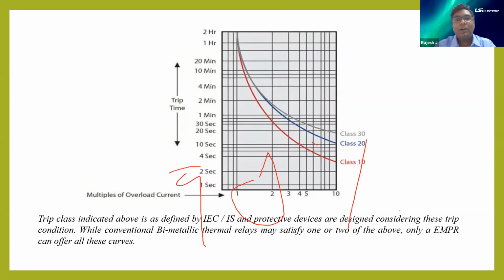Now, as we see, for different loads or different strokes, if you see the curve here, as current increases, trip time varies. They are called class 5, class 10A, class 20, class 30. It's defined based on the tripping time. The above chart shows the IEC and IS representation. It's a protection device characteristic given by IEC and IS: what is the time for the current increase versus the tripping characteristics? A single bimetal relay will not be able to handle all different kinds of tripping curves.